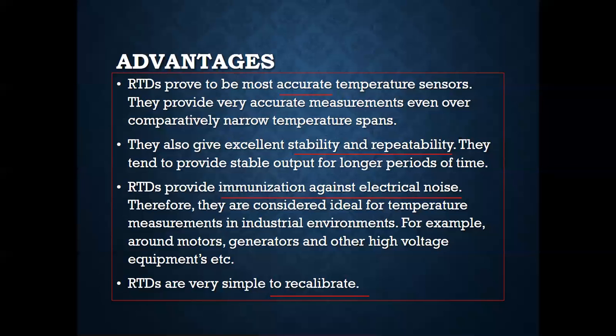That is why it can be used in industrial environments around motors, generators, and other high voltage equipment. Because RTDs are immune to electrical noises. That is why you can use RTD around motors, generators, and other high voltage equipment. And RTD can be recalibrated very easily.